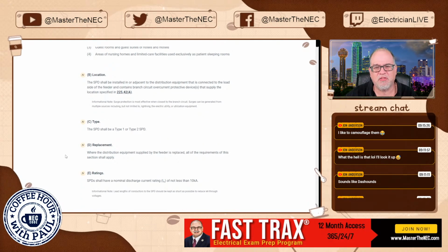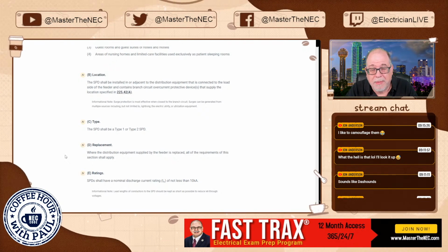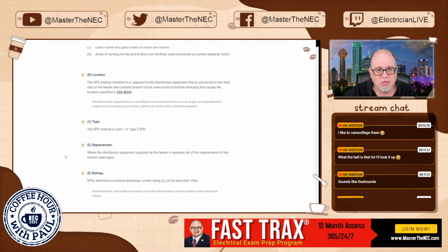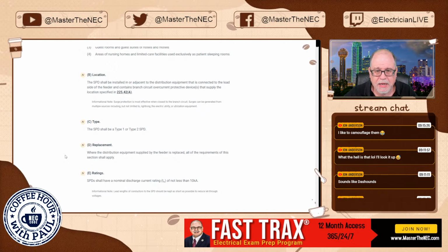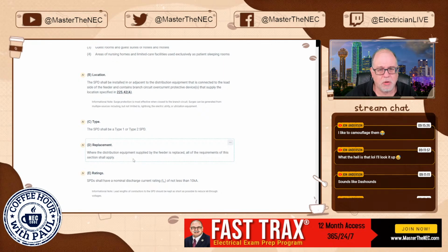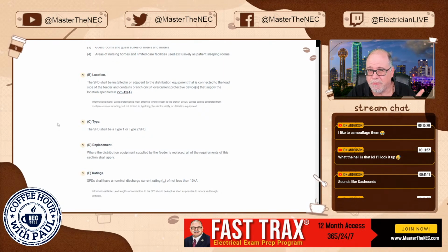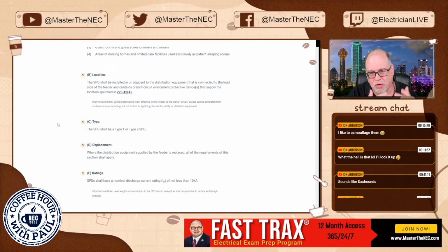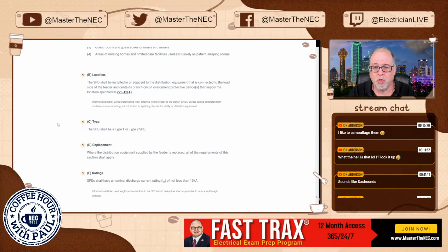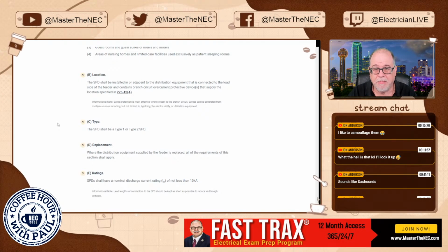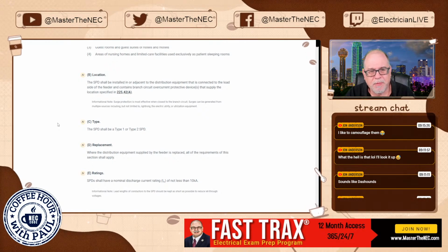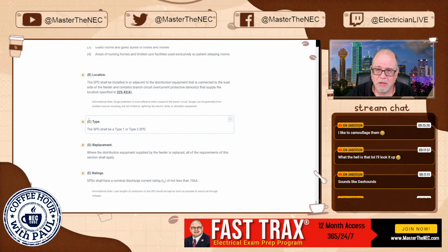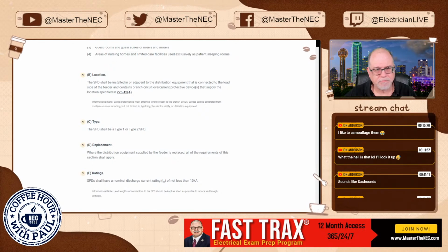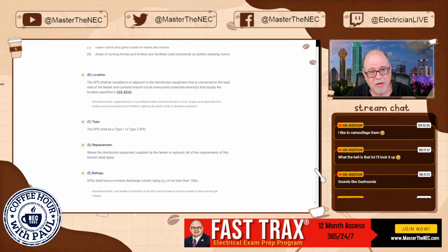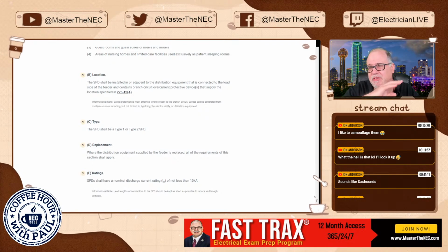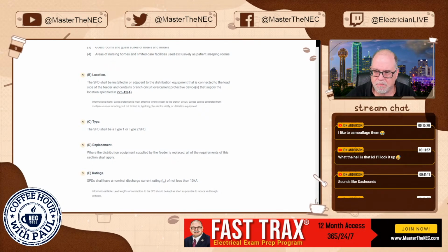All right, next would be the replacements. This is for all of you out there that are doing remodeling. So let's say you go to that apartment complex that's got those dwelling units or those dormitory units that are being renovated, and you're going to be replacing the distribution equipment. Well, this is very much similar to what we had for services when you upgrade or replace your service equipment. Same concept here for replacement. So if you replace that distribution equipment, maybe you're updating the dwelling unit, then you're going to have to install surge protective devices. It's going to be required. That's the replacement rule. And again, you're probably already familiar with that with the service and the SPDs. It's almost like a cut and paste concept.